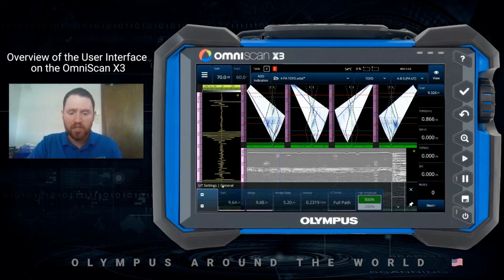So right now I'm looking at the general submenu, and there's a couple different things that I can do with this pop-up. One, obviously, it gives me access to all of the various parameters at the bottom, but then on the right-hand side, I can also scroll through all of the submenus that are underneath the UT settings menu. So I can access the general menu and click through here to the pulser, the receiver, the advanced, the beam menu. All of the submenus I can access from the scroll buttons that are here at this part of the menu.